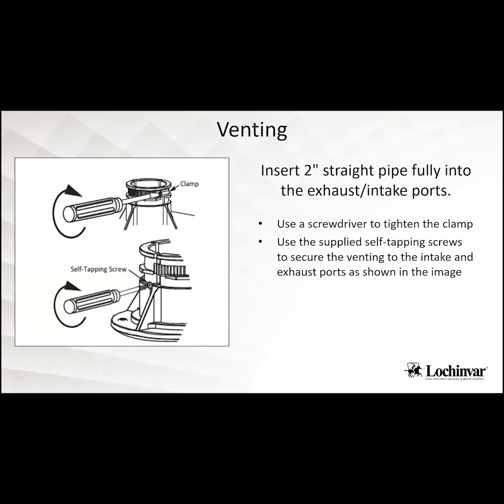And the top of the unit just has the band clamps that are around the exhaust and the intake. So you would just slide your pipe down in there. You can tighten down those clamps. There are these optional self-tapping screws that come with the unit that you can actually put through the side of that and into the vent pipe if you're wanting to lock that in there so no one can undo that and pull it straight out without having to take that self-tapping screw out. It's not required, but it is an added feature that they have there to prevent those vent pipes from coming out if someone was trying to rip it out of the unit itself.